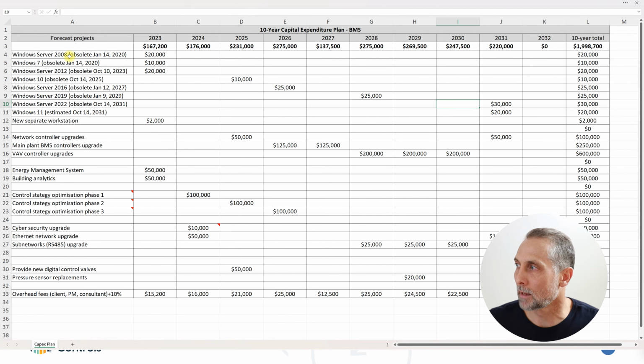At the top I have all the Windows Server operating dates that become obsolete, then network controller upgrades, main plant controller upgrades, VAV controller upgrades, energy management system, building analytics, and 3 phases of control strategy optimization. Phase 1 is chilled water, condenser water, hot water. Phase 2 is high-rise AHUs and VAVs. Phase 3 is low-rise AHUs and VAVs.